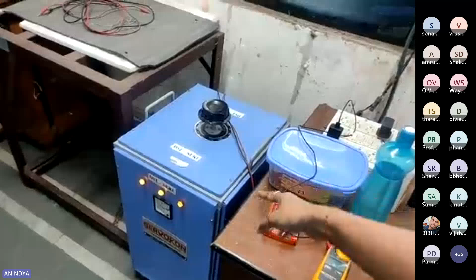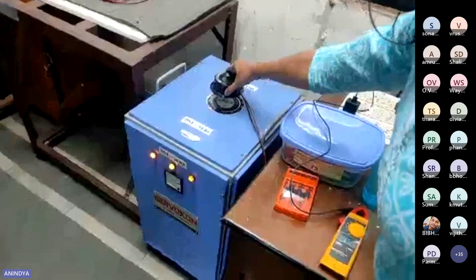This one is the auto transformer, and this is connected directly to the power supply. So by changing this switch, we can change the voltage, the AC bus voltage, according to our requirement. And this auto transformer is connected to this isolation transformer directly.